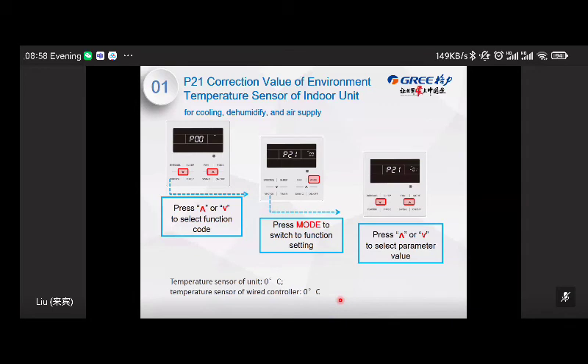Next one, P21, correction value for ambient temperature sensor of indoor units. That means you can use this function to correct, to modify the room temperature detecting. If you think, for example, in this room, the cooling performance is too cold, right? It's too cold. You can modify the ambient temperature sensor value so that the air conditioning control will be better for the customer feeling, right?